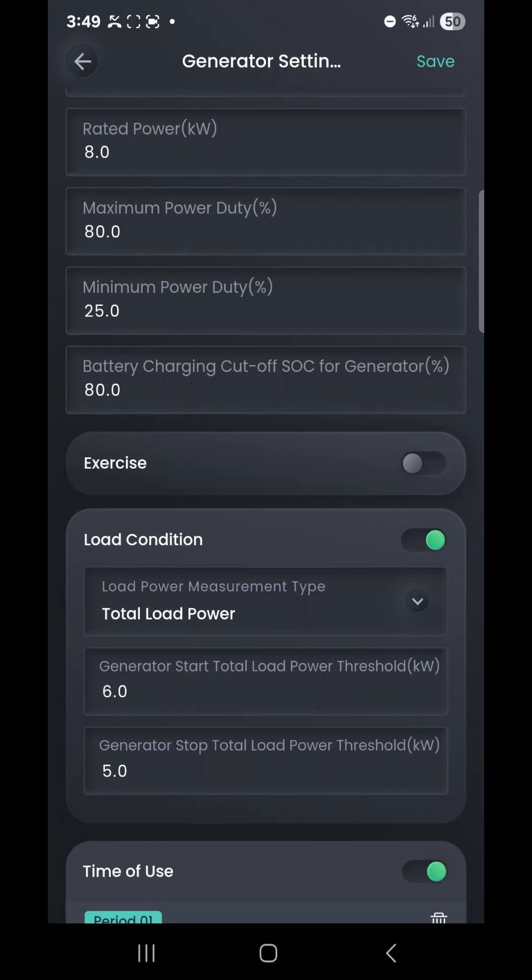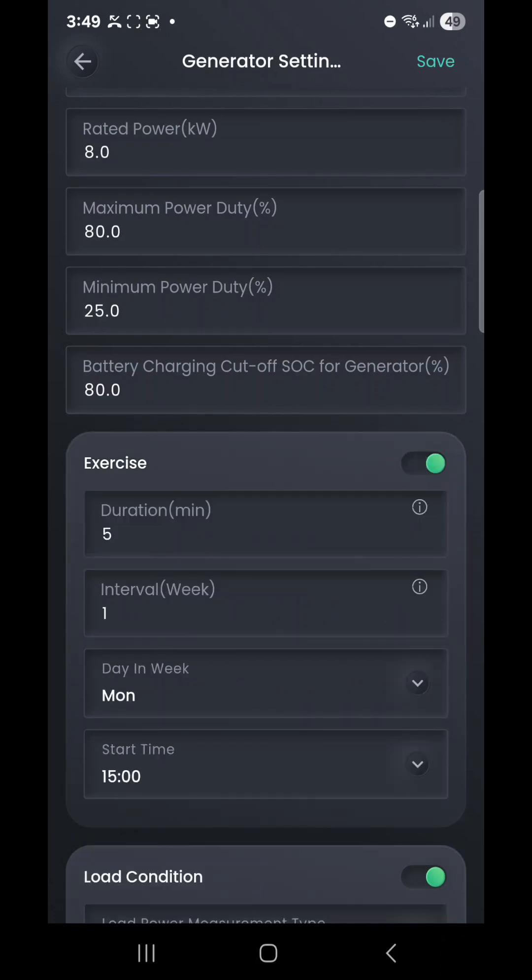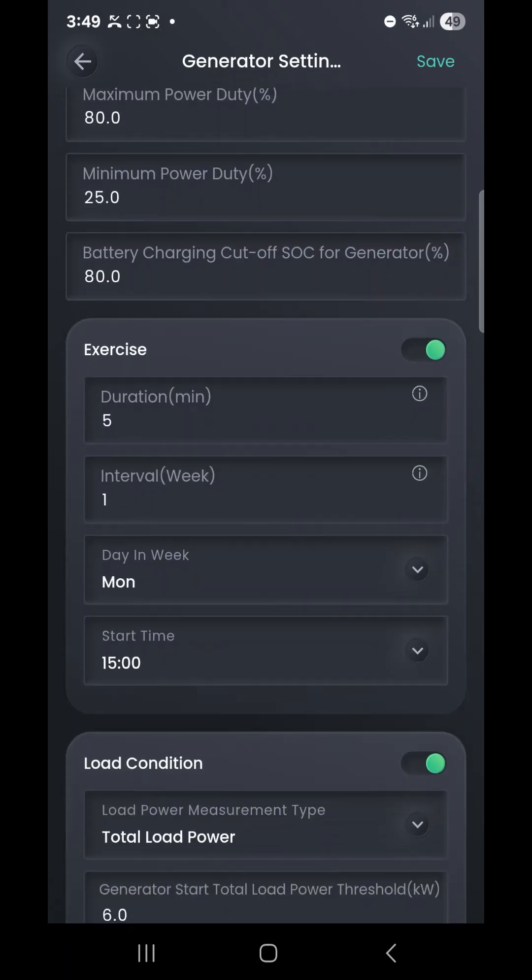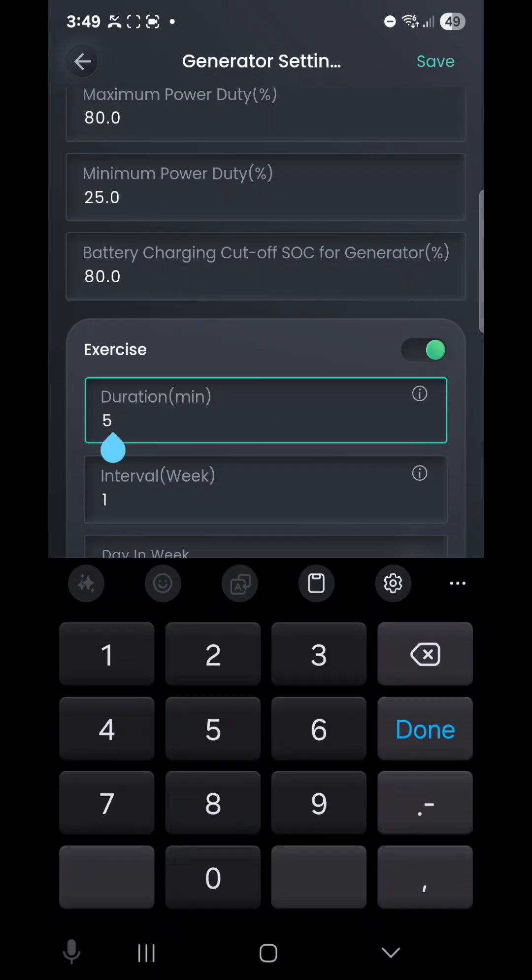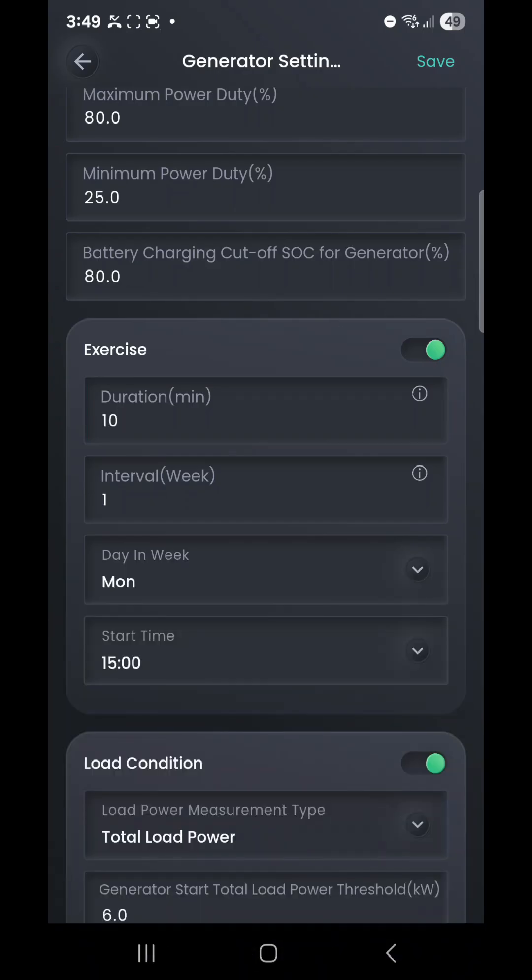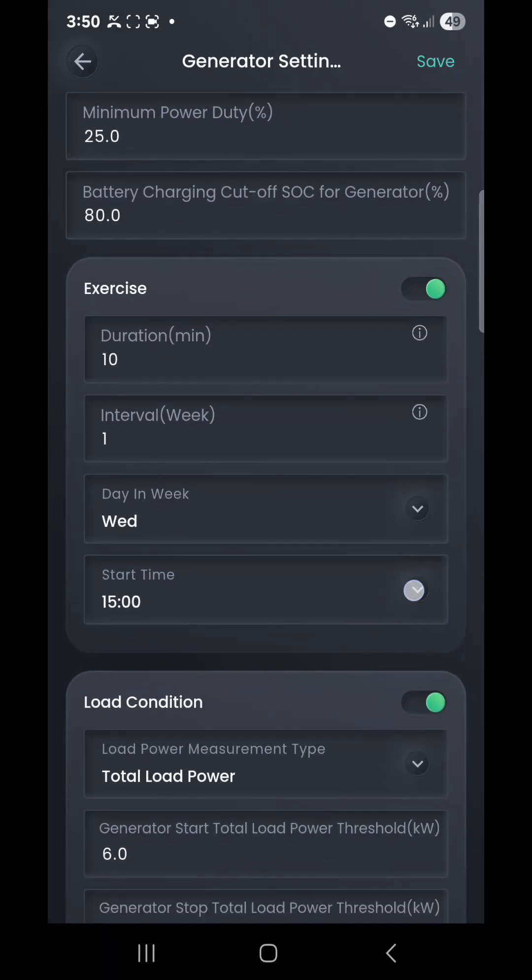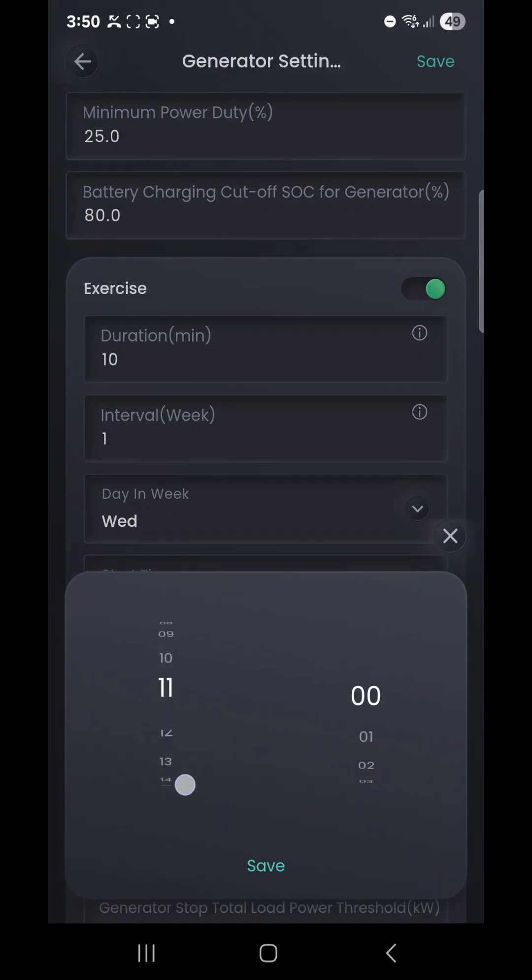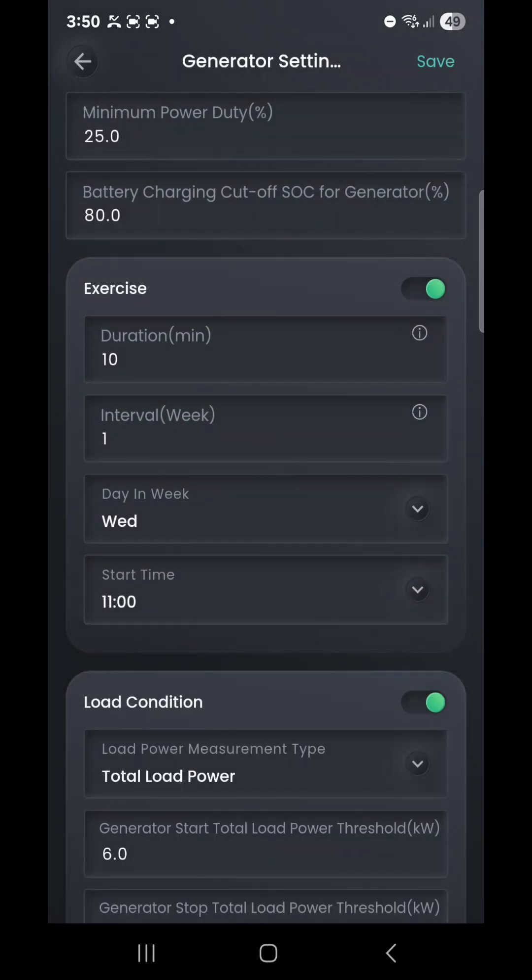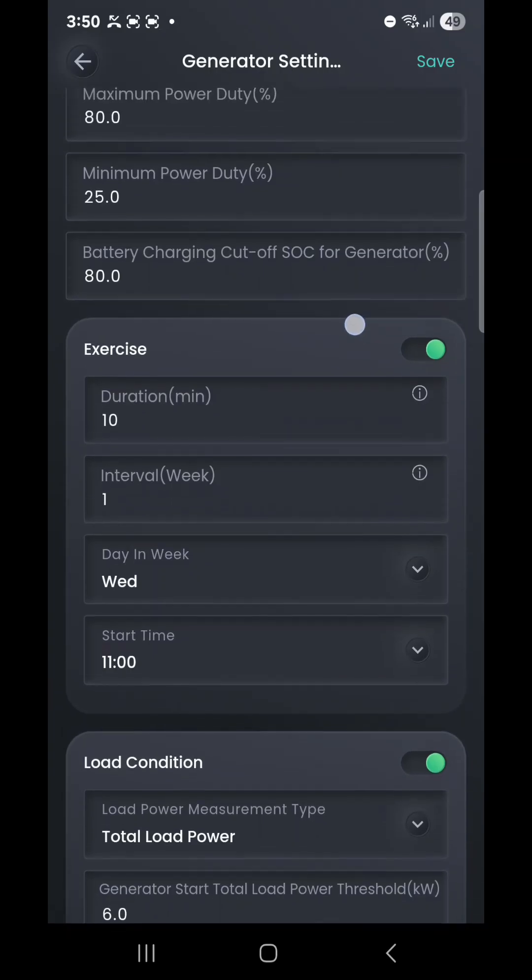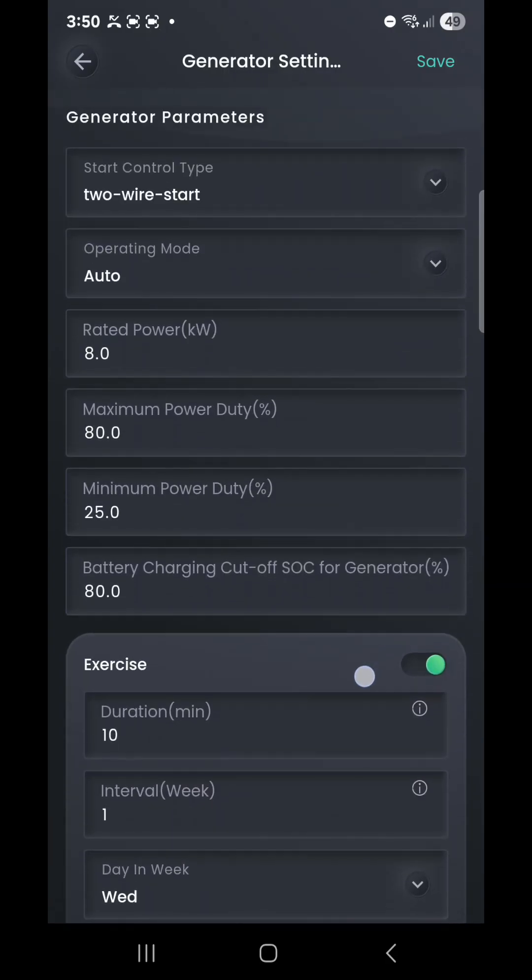The one last thing to cover in this tutorial will be the exercise feature, so we can enable this. What this means is we can tell the generator, if it's not being used very often—which is bad for generators—to fire up for a ten-minute period at an interval. We can go once a week, pick our day. Let's say we just want it to run on Wednesday once a week for ten minutes. We can tell it a start time, so we can say it's going to be a little bit less annoying if it fires up at 11 a.m. in the morning and hit Save. That will then automatically fire up that generator every single Wednesday at 11 o'clock and run for a period of ten minutes. That's really good to keep your generator lubricated up and make sure it's always there in the background ready to go.